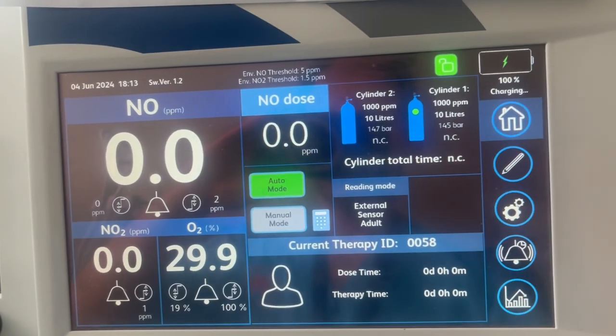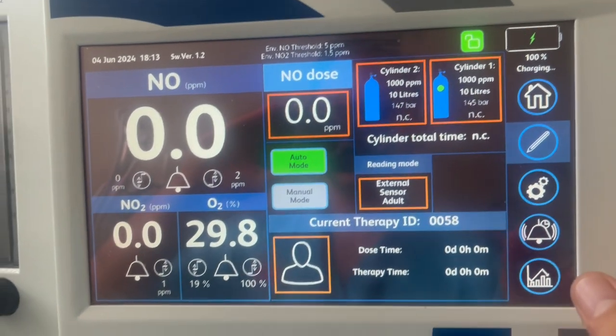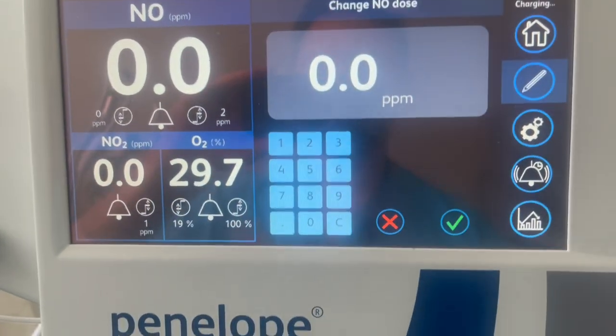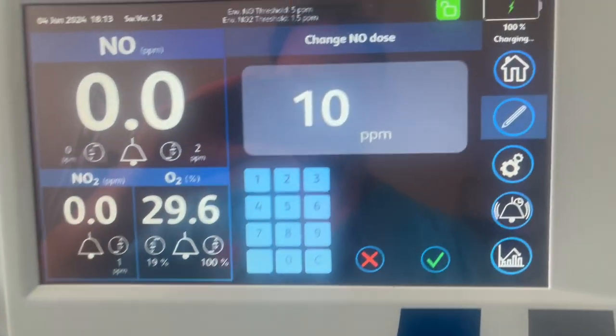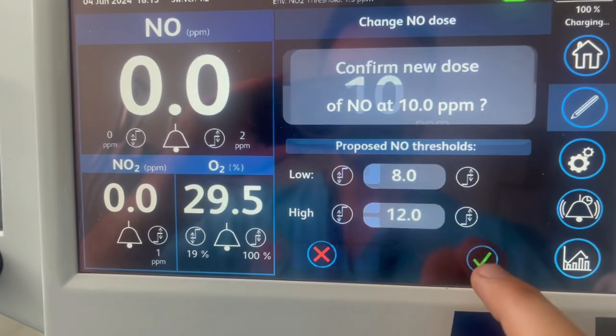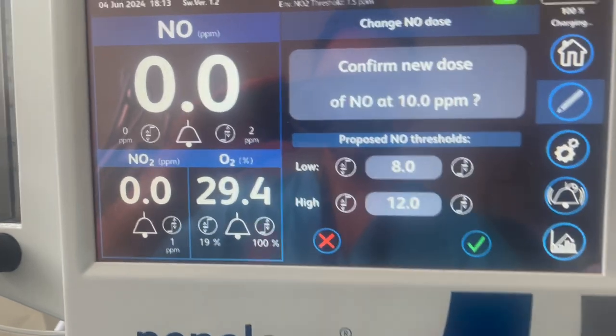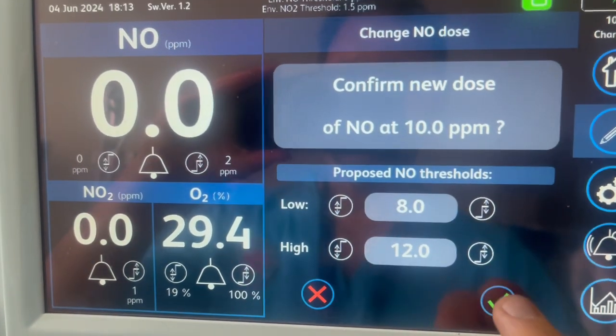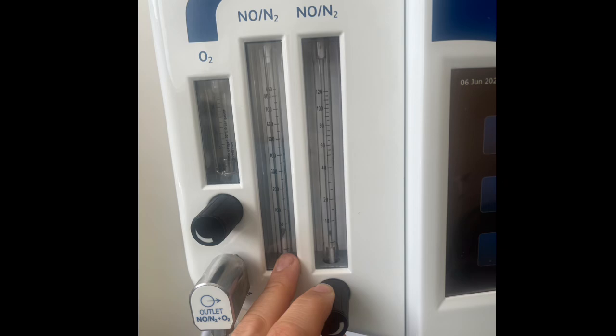To enter the nitric dose you want to start with, press the pen icon and press the box under NO dose. Enter the nitric dose you are starting with and confirm. If you're happy with the alarm limits, confirm by pressing the tick. The machine has given you an estimated flow value. These two flow meters are in fact one flow meter split into two. You can use the control knob to move the bobbin to the set flow that the machine has given you, and in this way, when you're manually bagging the patient, you are more or less giving the same dose.